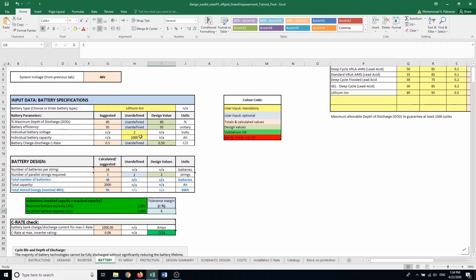Or you could change the battery type you're going to use if you want to minimize the number of batteries. Notice that making this change a little bit, up to 83 amp hours less than the capacity required by the system, could reduce the number of batteries the system was suggesting from 72 to 48 batteries. It's a significant saving in the capital investment required for this system.